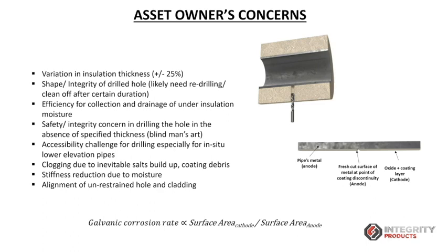And in the worst case scenario, this small scratch on the pipe could turn into a pinhole in a few weeks or few months, and the pipe will start leaking from that location. So here is the consequence of using the drilling in that jacketing.